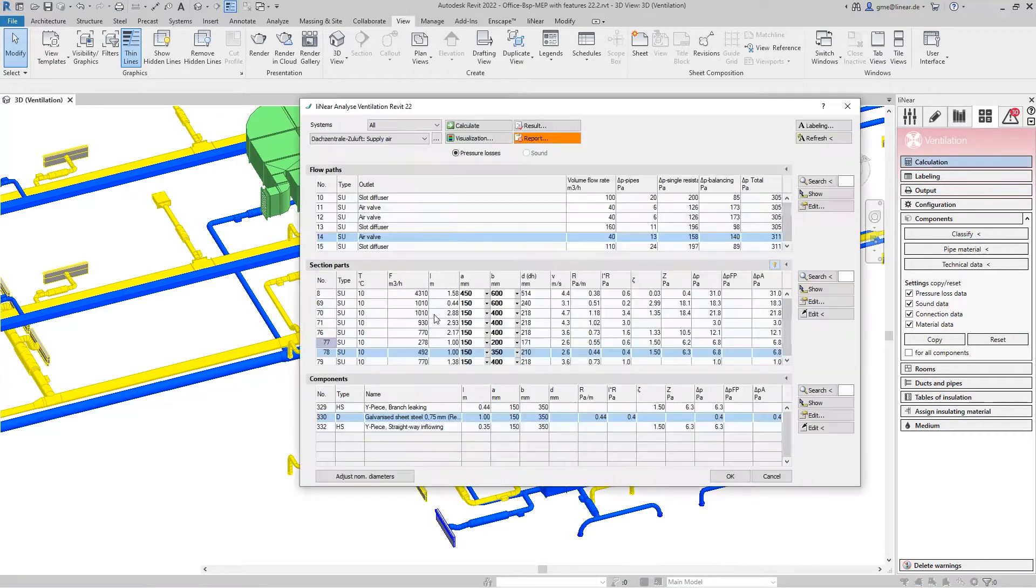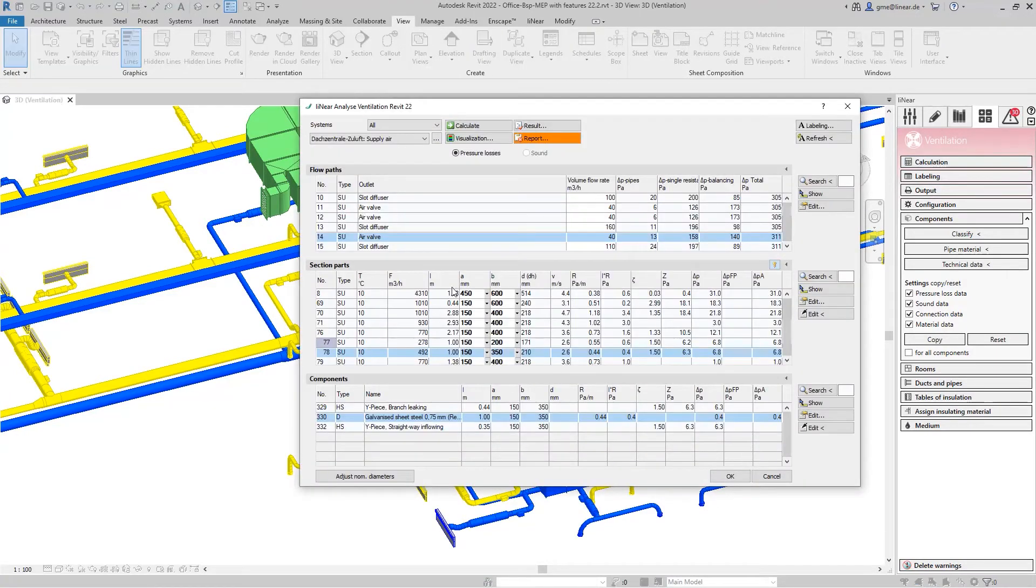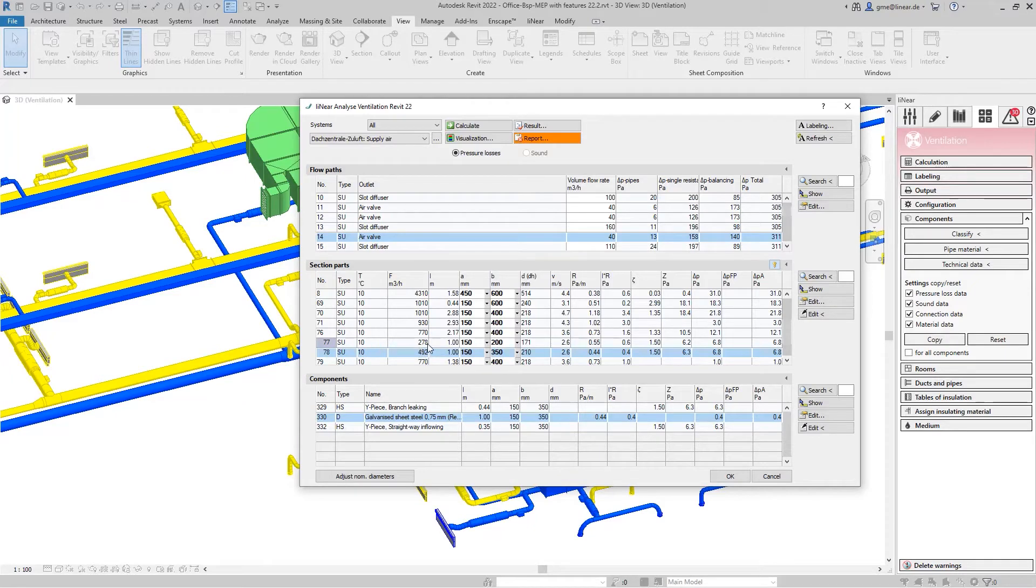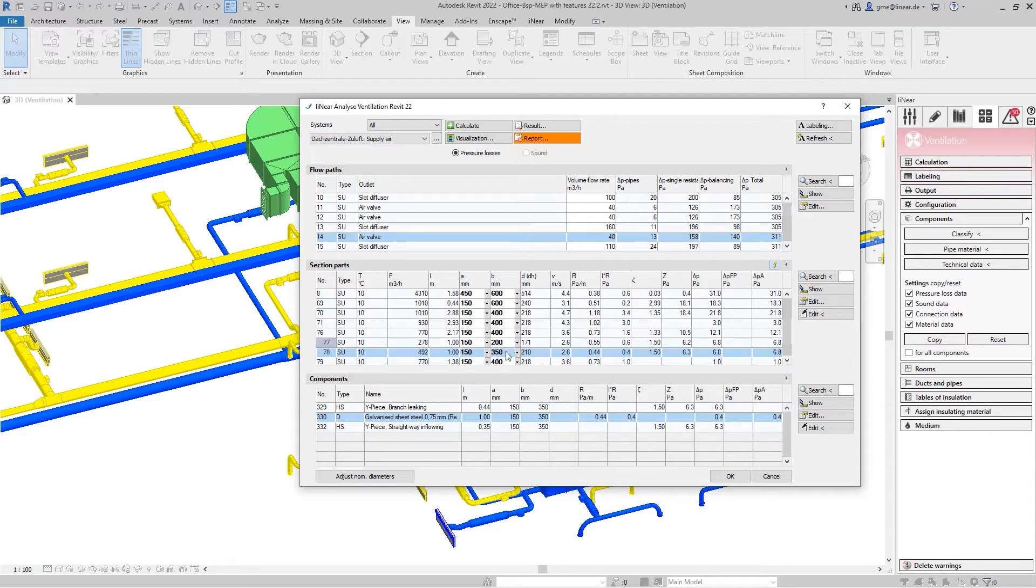However, if we now look at the situation on the first floor, we see that the airflow conditions are different. Because of the different sizes of the ducts, we also calculate a different volume flow. So here for the smaller cross-section, 278, and for the larger duct, 492 cubic meters per hour.